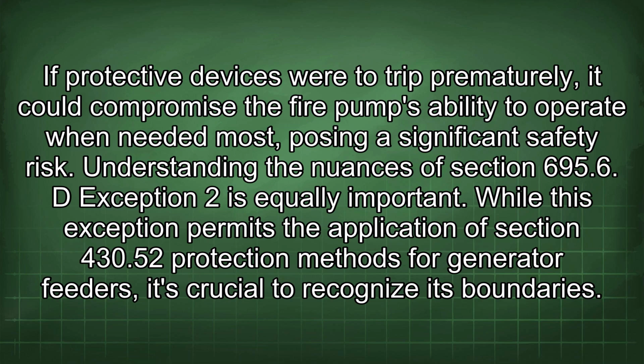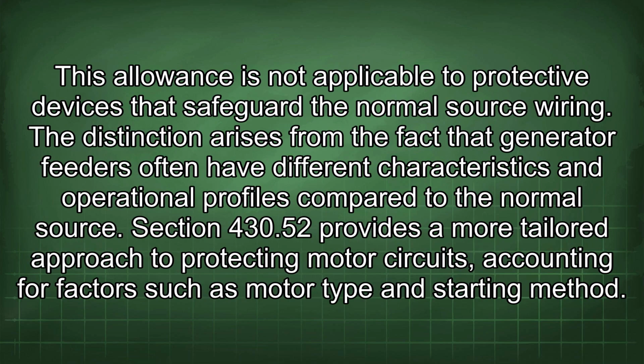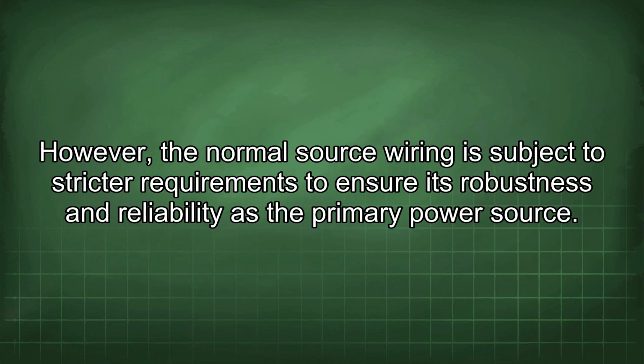Understanding the nuances of section 695.6, exception 2 is equally important. While this exception permits the application of section 430.52 protection methods for generator feeders, it's crucial to recognize its boundaries. This allowance is not applicable to protective devices that safeguard the normal source wiring. The distinction arises from the fact that generator feeders often have different characteristics and operational profiles compared to the normal source. Section 430.52 provides a more tailored approach to protecting motor circuits, accounting for factors such as motor type and starting method. However, the normal source wiring is subject to stricter requirements to ensure its robustness and reliability as the primary power source.